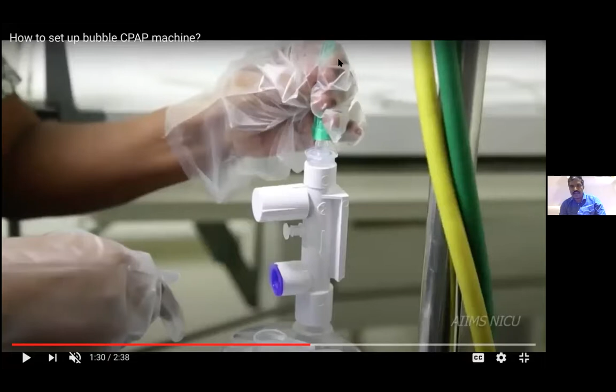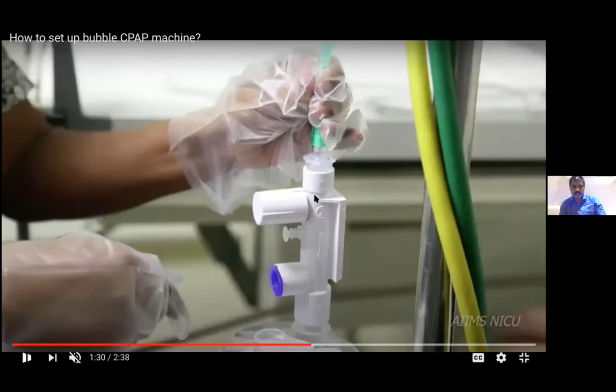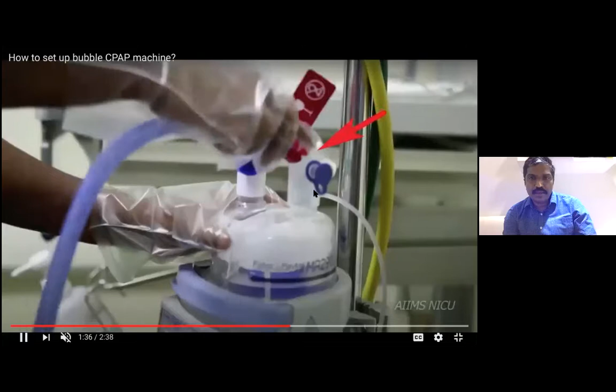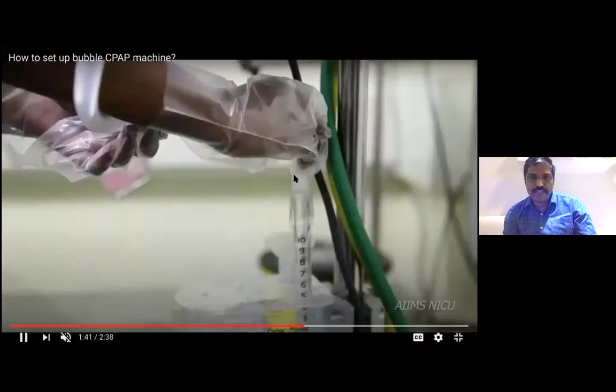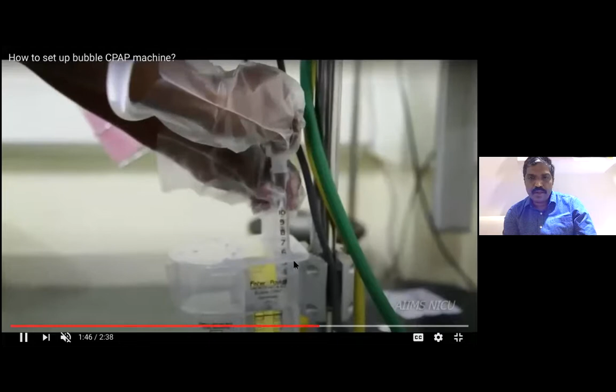And here you are connecting the gas from the blender to the bubble chamber to the humidifier. So this green tube is connecting gas from the blender, from the flow meter, to the humidifier chamber. From the humidifier chamber, this is the inspiratory limb, the blue wire. Now from the inspiratory limb, you seal using the expiratory limb, which is white, and seal the expiratory limb to the bubble chamber. Now when you seal it, you should be able to see the bubbles. Earlier no bubbles were there because there was some leak.